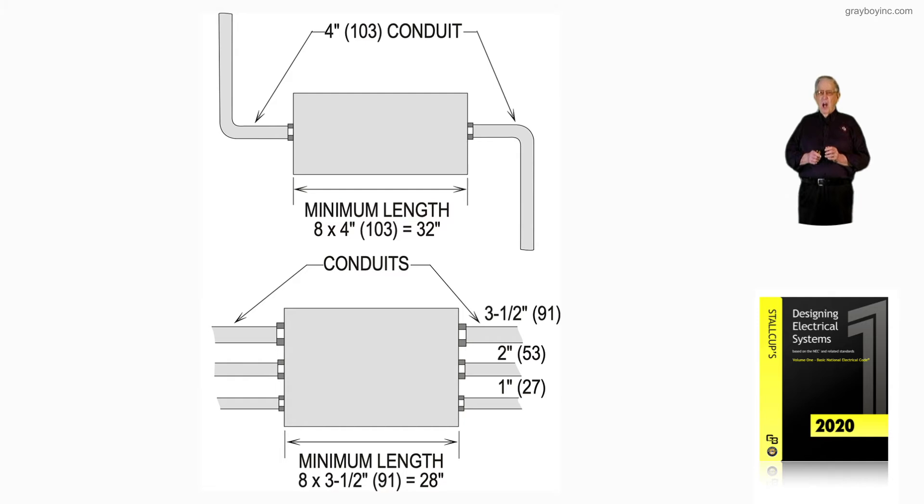Notice the top illustration, it's a straight pull. Now you have two 90s on the conduit, but it's still a straight pull, and it's eight times the size of the conduit. So you have a four-inch conduit, four times eight is 32 inches.